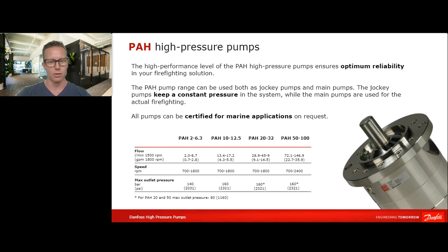And at the heart of the high pressure water mist skids, we have the high pressure pump sitting. Our pump is called PAH. It's for drinking water, and it's a positive displacement pump. It means that the flow it provides is directly proportional to the speed. So the higher the rotation, the more flow it provides. It's made of stainless steel, and it makes it highly reliable. This is, of course, key in firefighting applications, that whenever there's a fire, it simply must start.